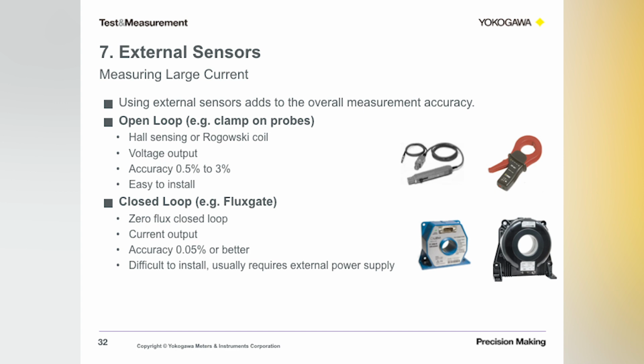Typical power analyzers or power meters will be able to measure currents as high as 50 amps or 55 amps. But beyond that, you're going to have to resort to using some type of external device to bring those large currents down to an instrument's measurable level. Using external sensors is not a bad idea, and sometimes it's a necessity. You have to be careful when choosing one, because it will add to the uncertainty of your overall power measurements.